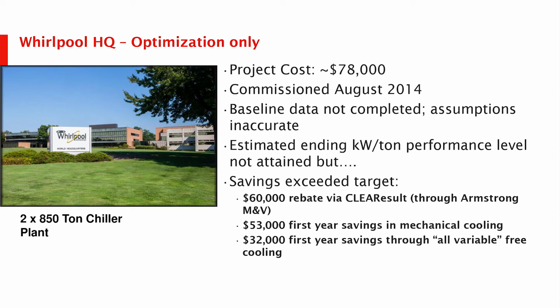The building next to it complained because it was ugly. So they built a screen so that the people wouldn't have to look at it. And then to compensate for that, because they go like, this isn't working well, they piped air in from the underground garage. I'm not the smartest guy in any room, but I know that didn't help because now they're piping all their warm exhaust air from the garage into the cooling tower to give it extra air. So they get all the superheated air from the underground parking garage piped into the cooling tower. And so we explained to them that wasn't helping either.